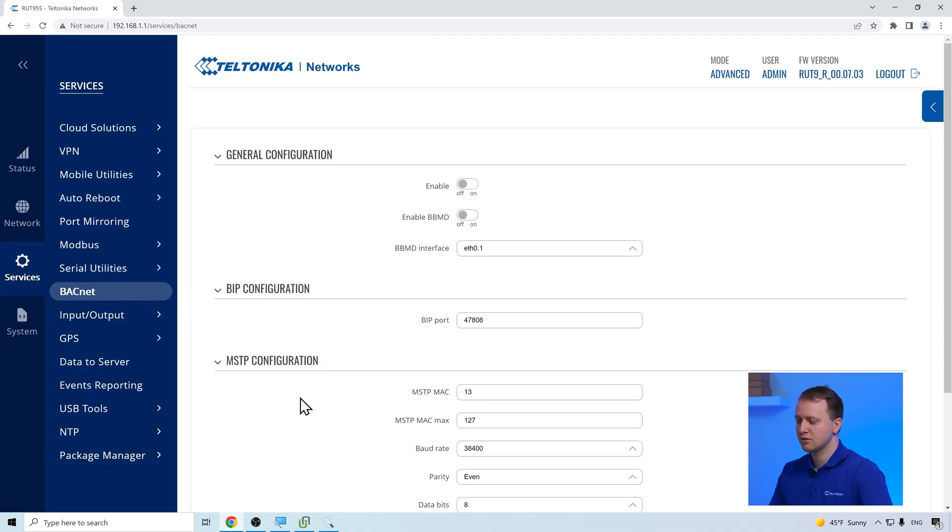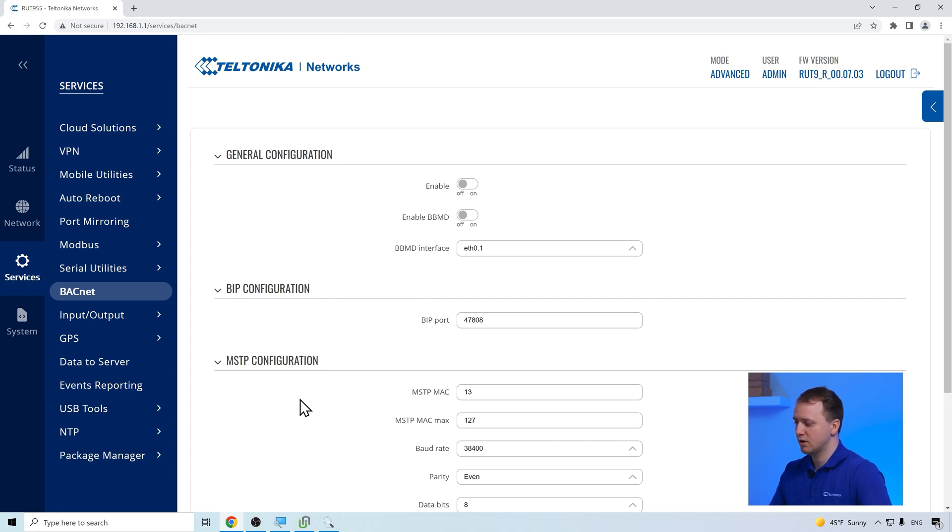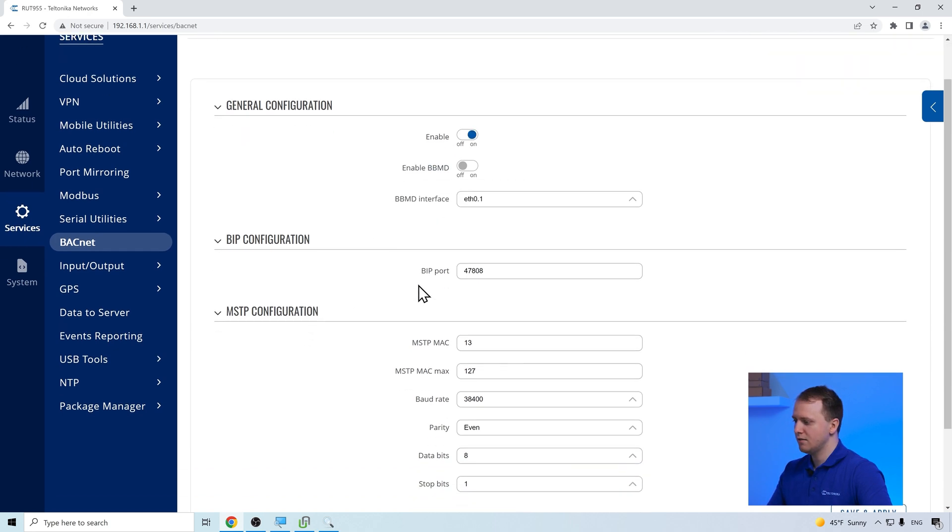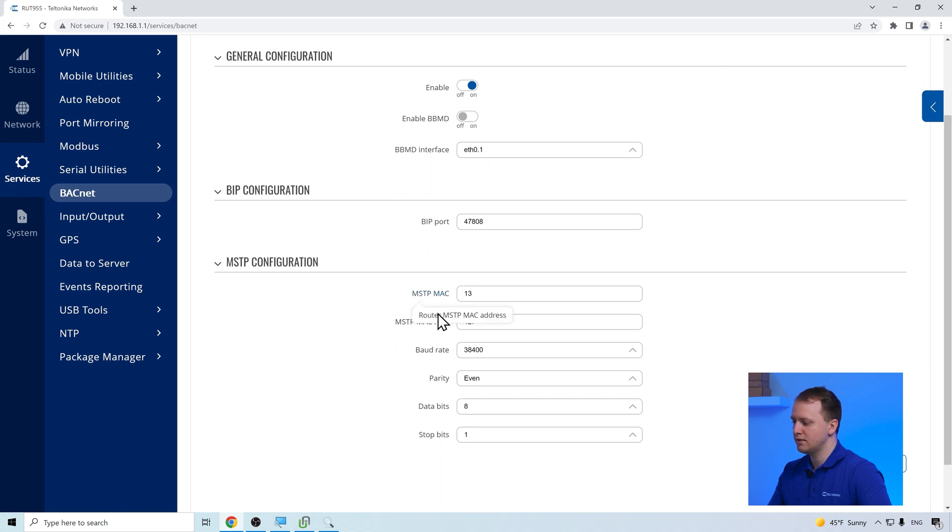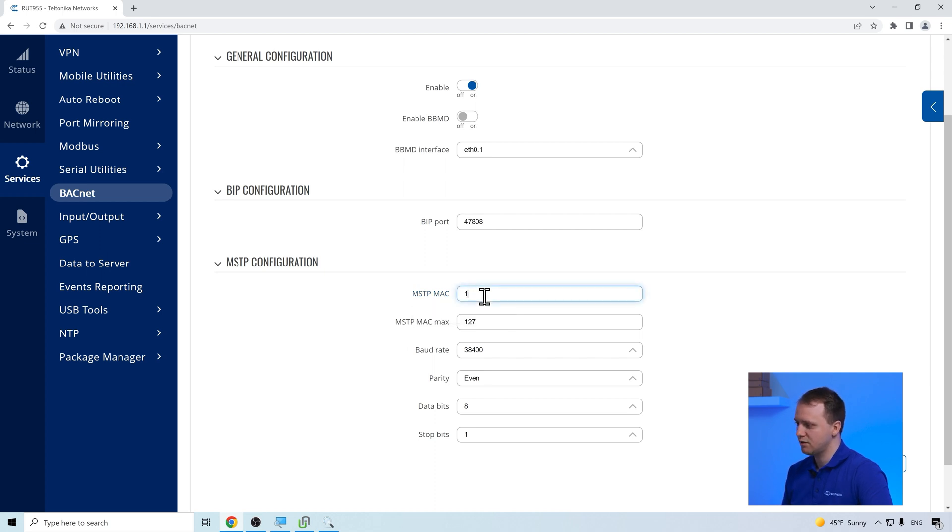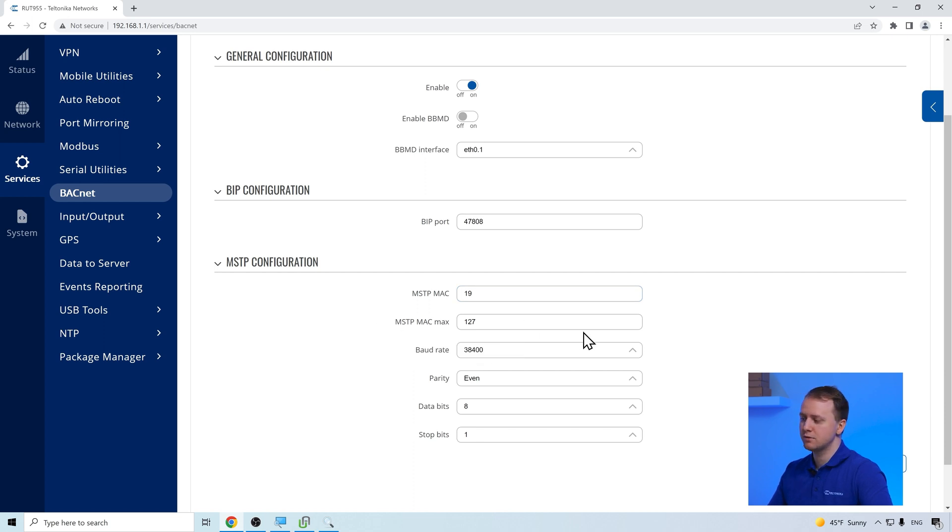The BACnet configuration is pretty straightforward. In our example, we are going to configure BACnet over IP. For that, we need to enable the BACnet service. Input the required serial information. In our example, all default values will suffice except the MSTP MAC address, which needs to be set to 19. After that, just save the configuration.